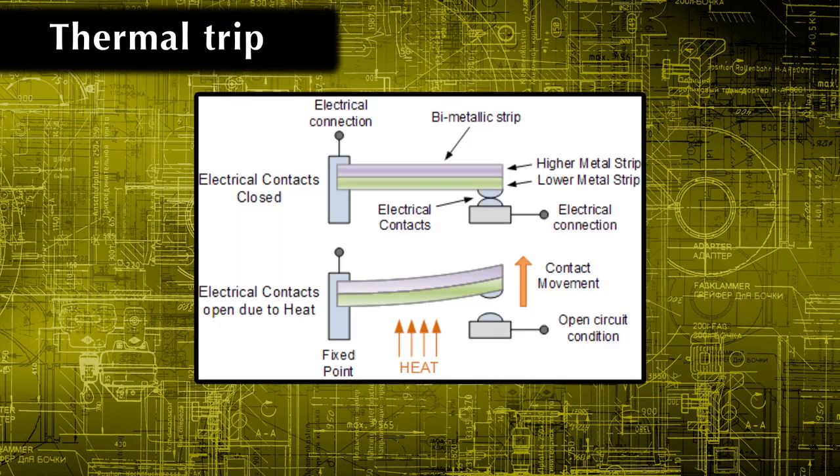While the thermal part consists of a bimetallic strip. So when overload current passes, it causes this strip to heat and bend. If it continues to a certain set duration, the strip will bend enough to trip the circuit.